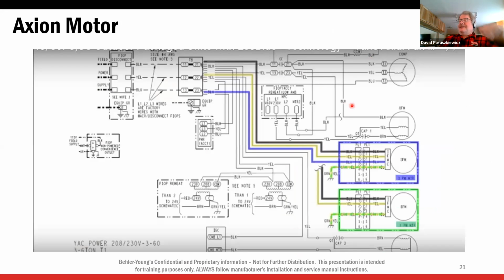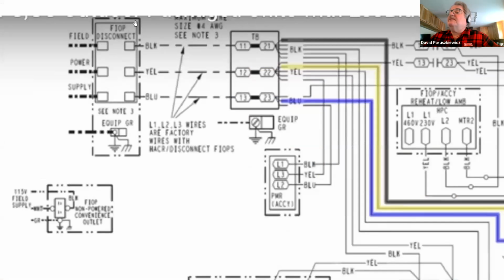All right. This is an ECM blower motor. What does that mean? It means it has power to it all the time, just like the blower motor in your furnace. There's no contactor. There's always line voltage on the motor. So if you take a look right up here is my terminal strip, right? So here's my disconnect. Here's my L1, L2, L3 coming in. There's my main terminal strip in the unit.